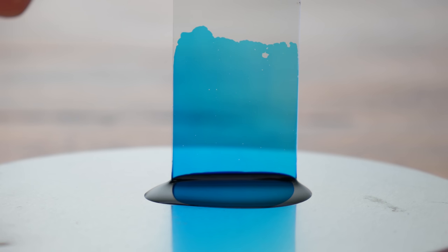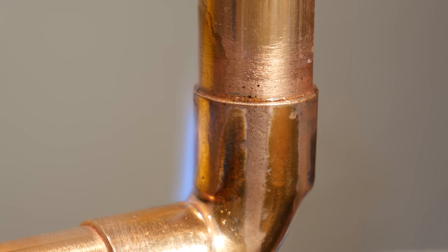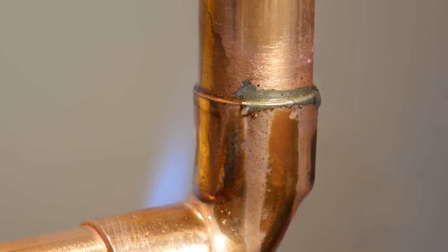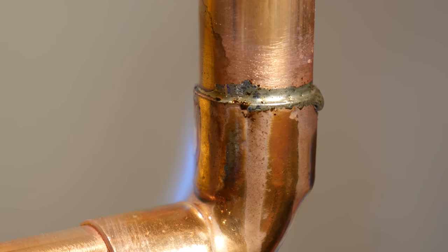Think of it like a dry paper towel. As soon as it's dipped in water, the water goes towards the dry area. So, to make sure you're getting proper capillary action, heat the fitting and not the solder, and you'll see it get drawn in just like this.